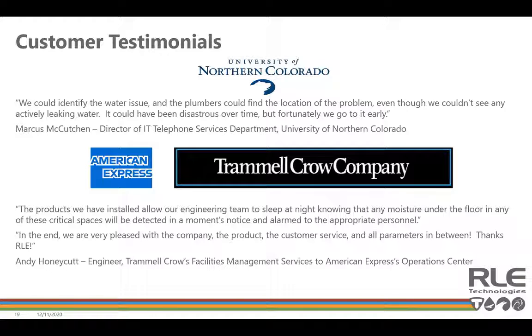So once the RLE SeaHawk leak detection system was installed, it was fully operational. Go figure, a leak occurred in the telephone switch room. The RLE system detected the water, and of course, as you saw earlier, the controller issued an alert. McCutcheon checked the area above the drop ceiling, and he did notice some dampness on the cable and on one of the ceiling tiles. He notified the campus plumbers, who at that time couldn't identify an immediate leak. So ultimately, they determined that there was a crack in the floor sink in the custodian's closet, which was causing that leak. And go figure, it was right above the long distance recording equipment area.